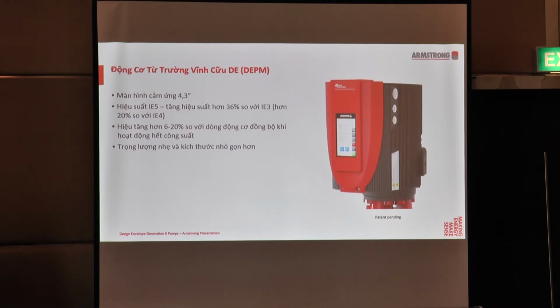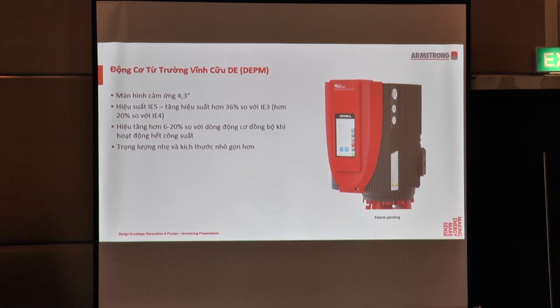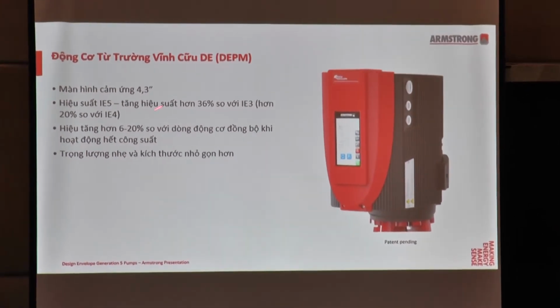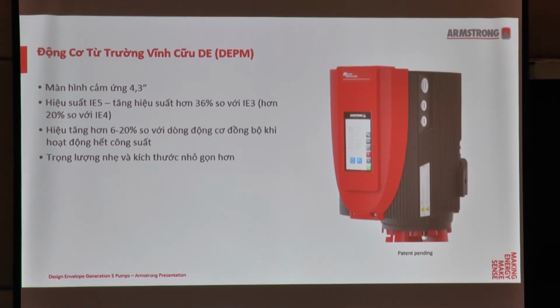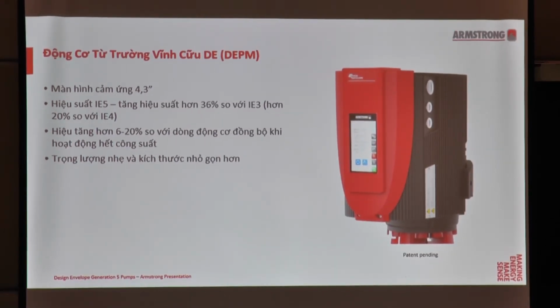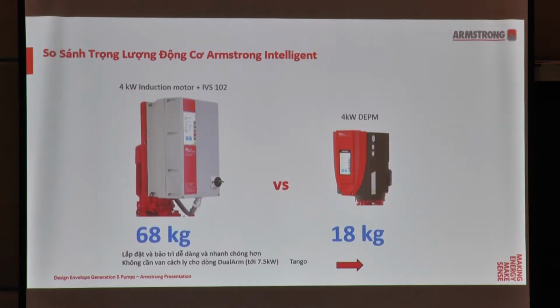And compared to the traditional induction motors and also the drivers, the separated inverter installations, it would be the efficiency improvement for about 6 to 20%. And also we have the possibility to reduce the weight and also the physical sizes. Yeah, this is a comparison for the 4 kilowatts, the induction motors plus the IVS inverter compared to the DEPM motors. You can see this is 68 kilograms, but for DEPM it's only 18 kilograms.